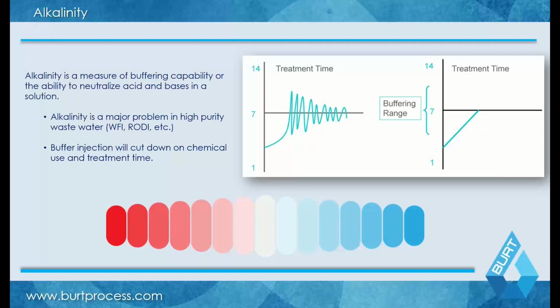So when you use that in a process and it mixes with a chemical, when you dump it down the drain, you now have what's referred to as low alkalinity waste. And this is very true in things like WFI stills, pharmaceutical industries, also ultra pure water, and the semiconductor industry. There simply is no buffering capacity for your system.